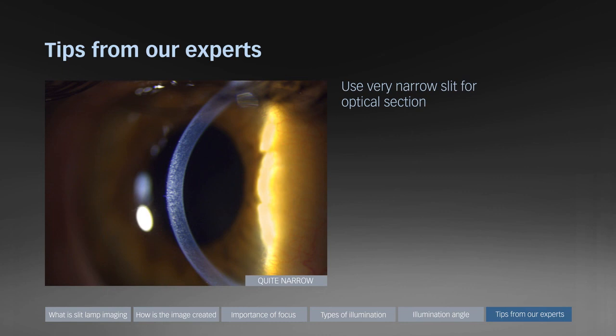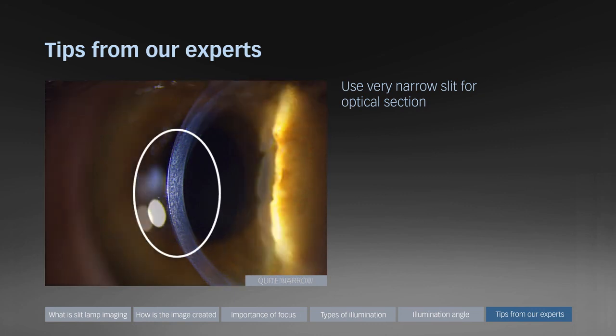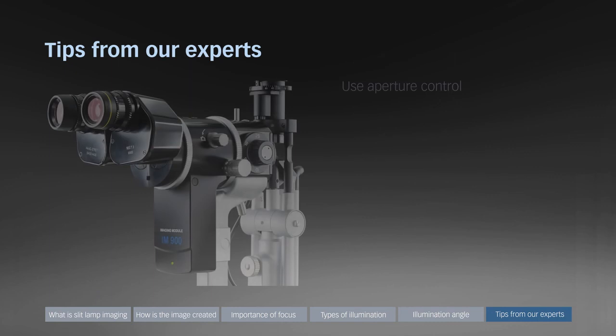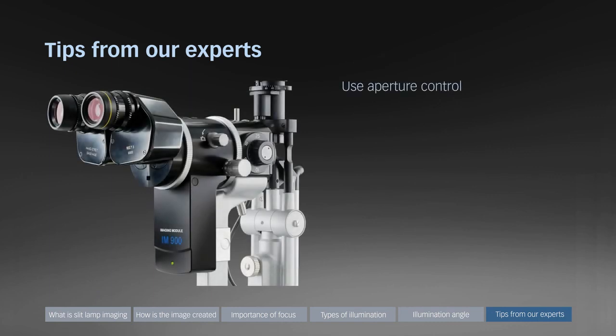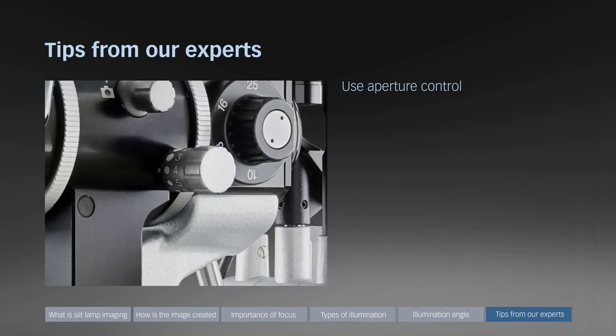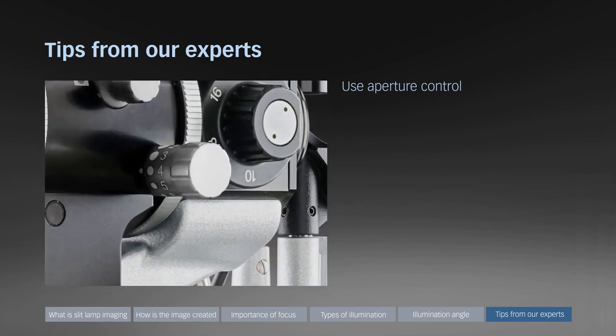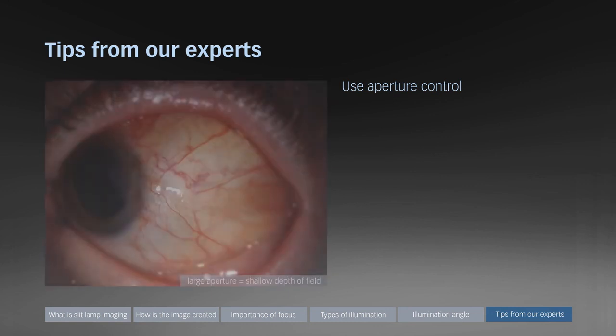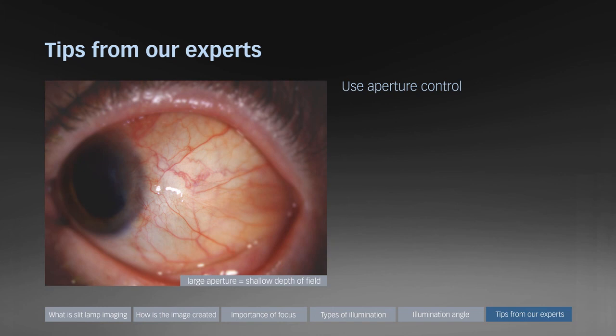Here an example of a quite narrow slit where no detail in the cornea is visible, and here an example of a very narrow slit which reveals the different layers of this healthy cornea. Use aperture control — the Haag-Streit IM900 imaging module provides aperture control. Use a large aperture if little light is available and a small aperture if deep depth of field is required. Here an example of an image with shallow depth of field, and here the same eye with deep depth of field.